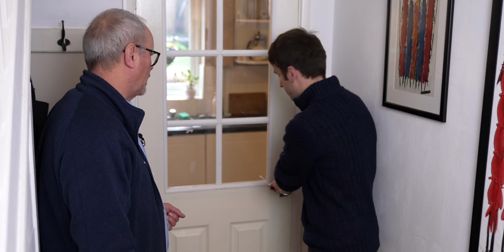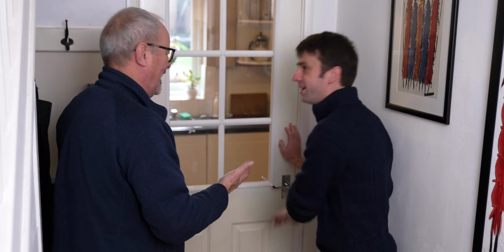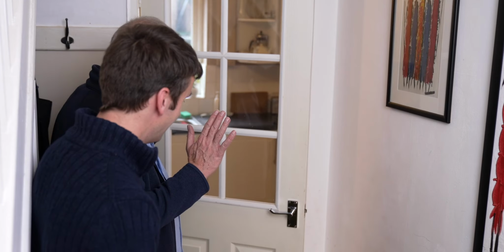So the way we find out precisely where the leaks are coming from: close all the doors in the house while the fan's running, and open the doors one at a time. You see the pressure there? You feel? Oh my God! That's not like a slight leak. That's wind coming through here. Yeah. So that wind's got to come from something, and it's cold. That is amazing. That isn't a little bit of air. That's a lot. So we've identified there's some big holes somewhere in the kitchen.